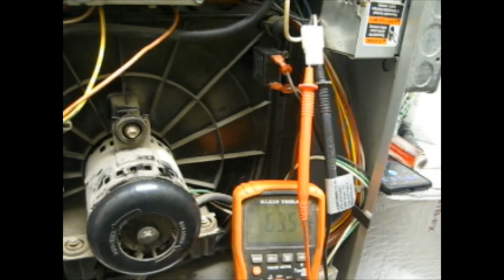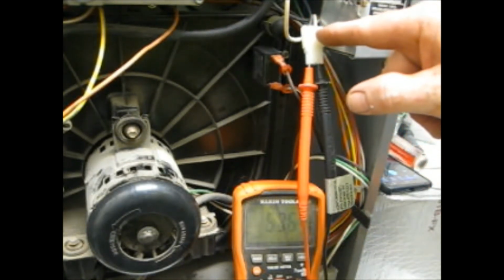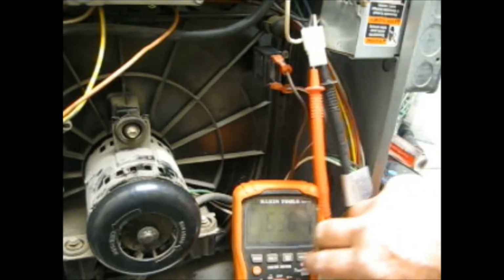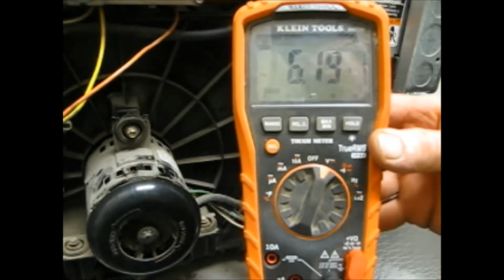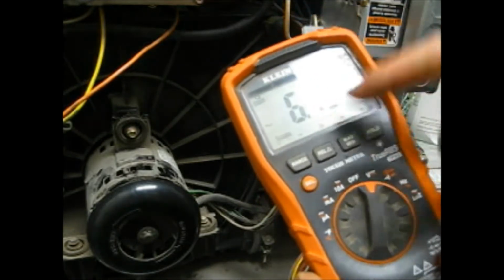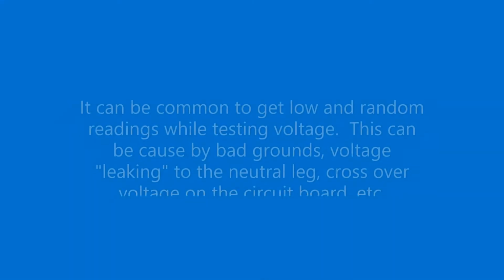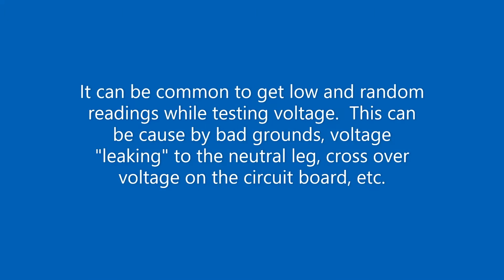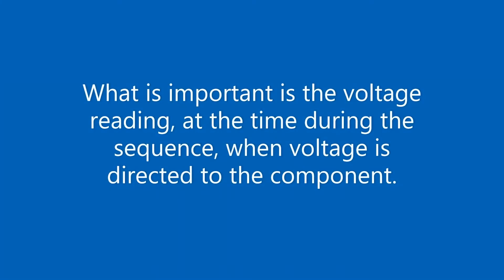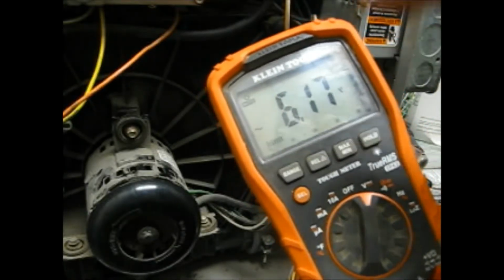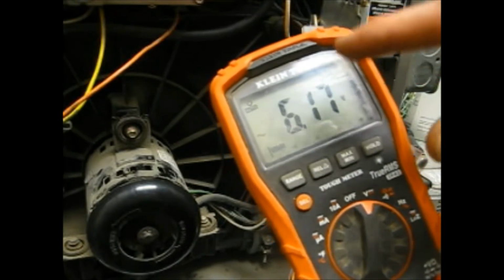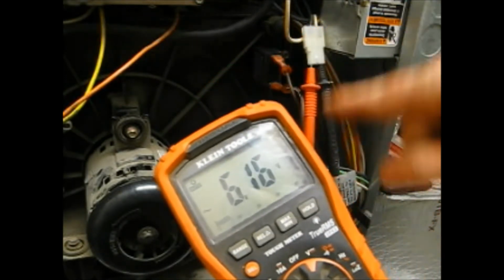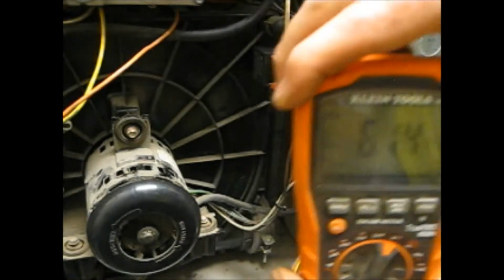Okay, we started the furnace up again. We got our voltmeter contacts inside the plug, and we have our voltmeter set up. Now what you're reading right here is this random voltage. What we're going to be looking for is 120 volts at the time you hear the contacts click to send power up to the hot surface igniter.